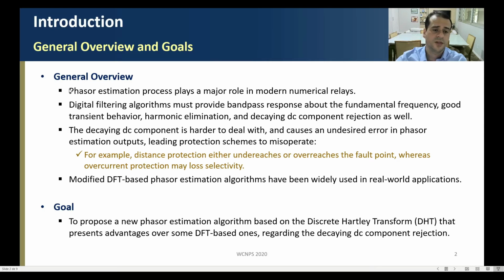It's well known that the phasor estimation process plays a major role in modern numerical relays. In fact, digital filtering algorithms must provide bandpass response about the fundamental frequency, good transient behavior, harmonic elimination, and decaying DC component rejection as well.